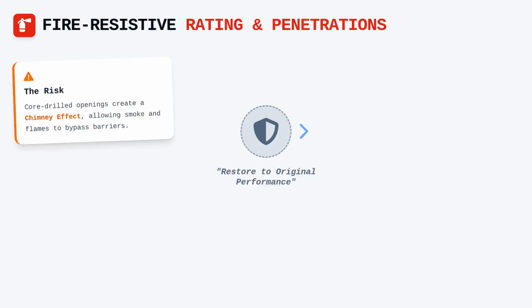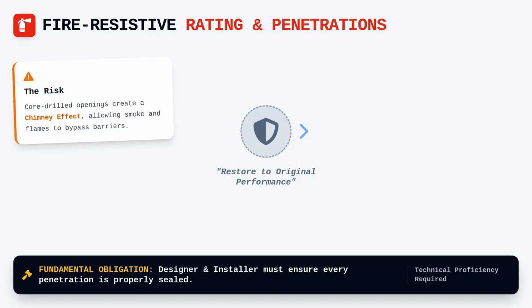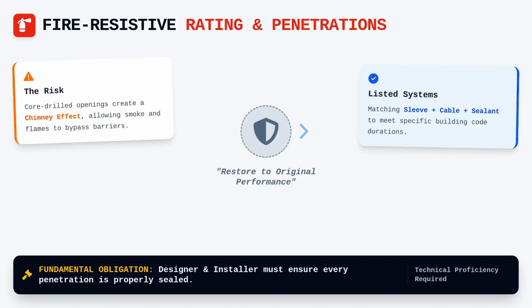The fire-resistive rating of the building is perhaps the most critical constraint in our planning phase, as any breach must be restored to its original performance level. When we pass cables through a core-drilled or sleeved opening, the remaining void creates a chimney effect that allows smoke and flames to bypass fire-resistant barriers during an emergency. It is a fundamental obligation of the designer and the installer to ensure that each penetration is properly sealed after installation using listed systems. These systems are tested to resist fire for specific durations, and the combination of the sleeve, the cable, and the sealant must match the requirements of the building code.